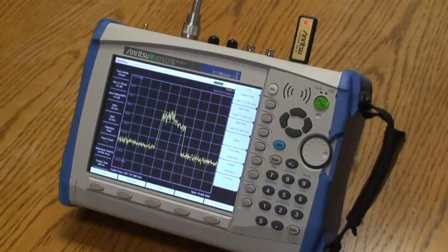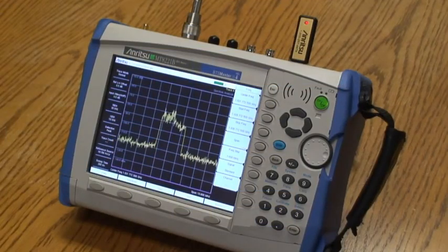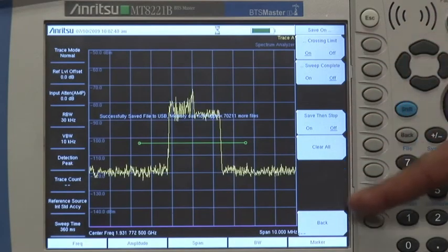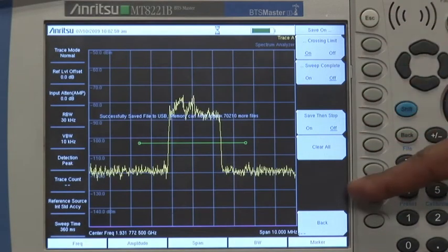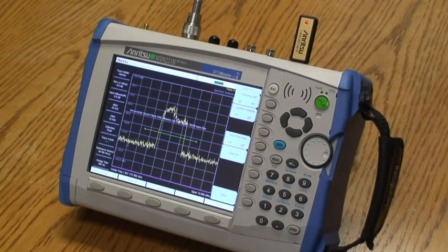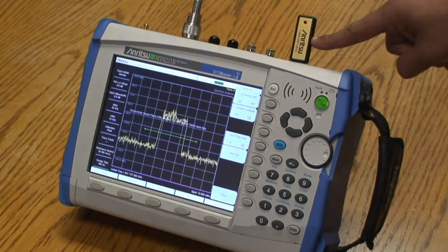Now you can with the spectrum analyzer in Anritsu Handheld Instruments. With Save on Event, you can set the spectrum analyzer to automatically save measurements which violate a preset limit line configuration, or just save all of the sweeps in a USB memory stick.